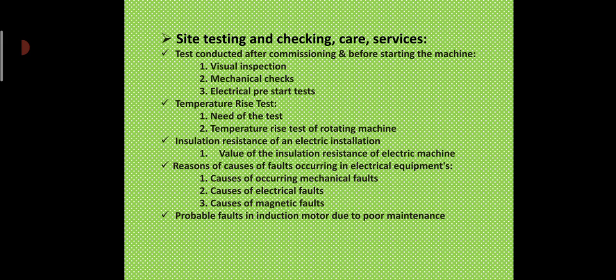In the second case, phase and neutral wires are connected together and connected to the L terminal of the megger. The E terminal of the megger is connected to the earth of the service line. Load, fuse and neutral link are kept connected. All the switches except the main switch are kept on. The handle of the megger is rotated and the reading is taken. It should not be less than the value found from the following formula: 50 divided by the number of points, in megaohm.